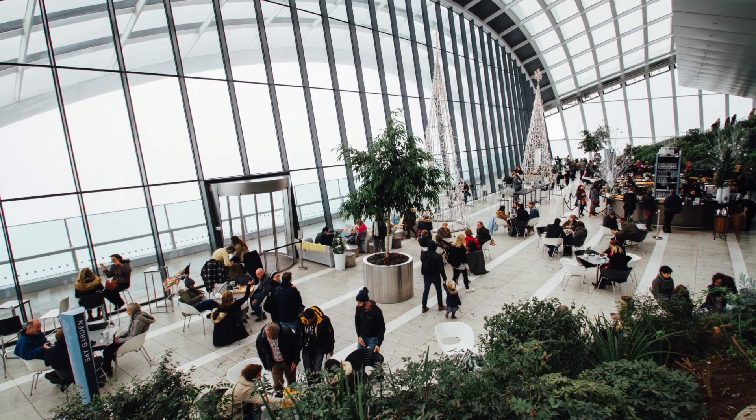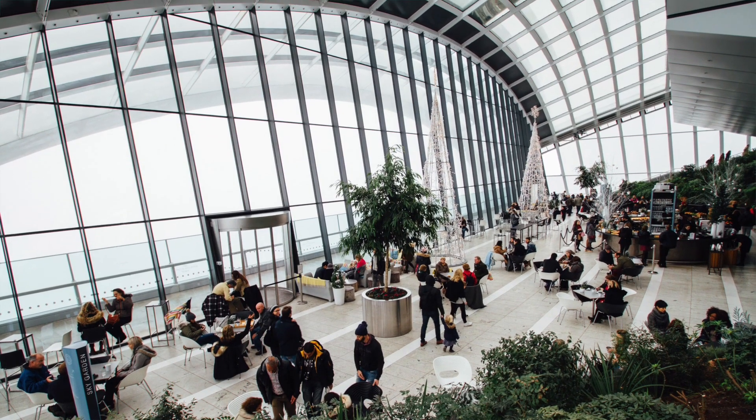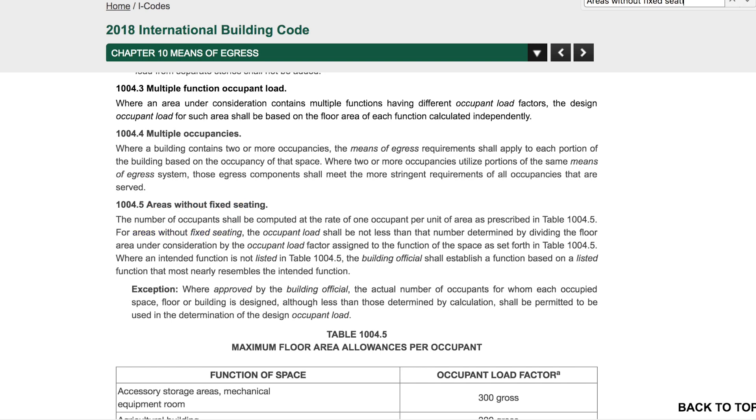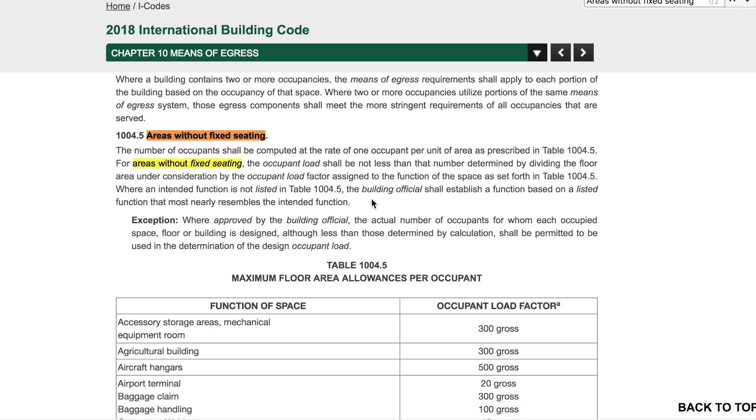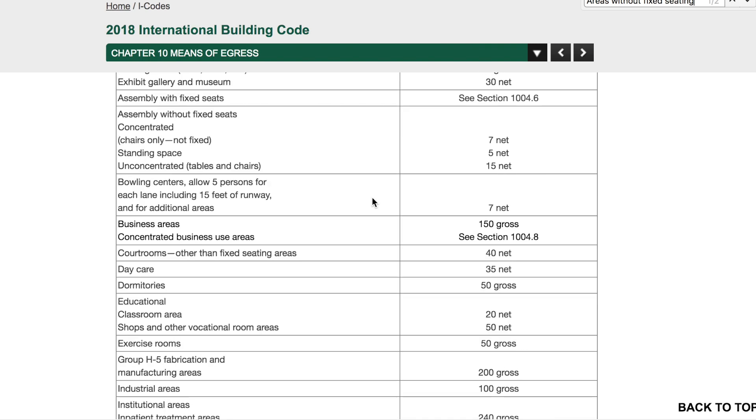In order to determine egress provisions, we need to figure out how many people are expected to use a space. In a space that only contains fixed seats, like a movie theater, it's pretty straightforward to figure that out. It can be done by counting the number of seats. But what about spaces without fixed seating? Well, another method is to use the occupant load factor table provided in the building code.